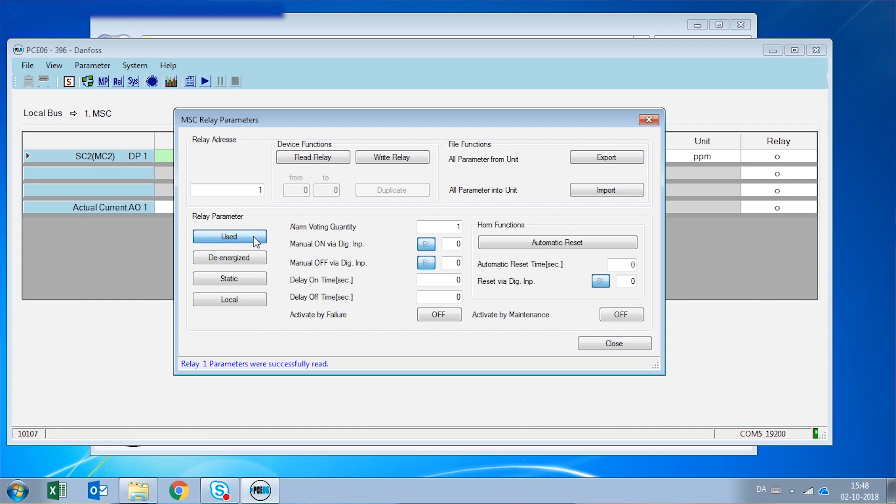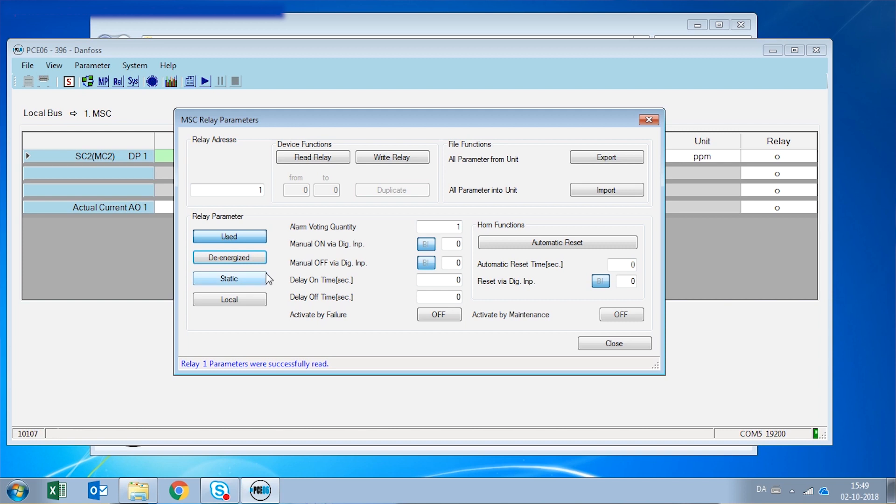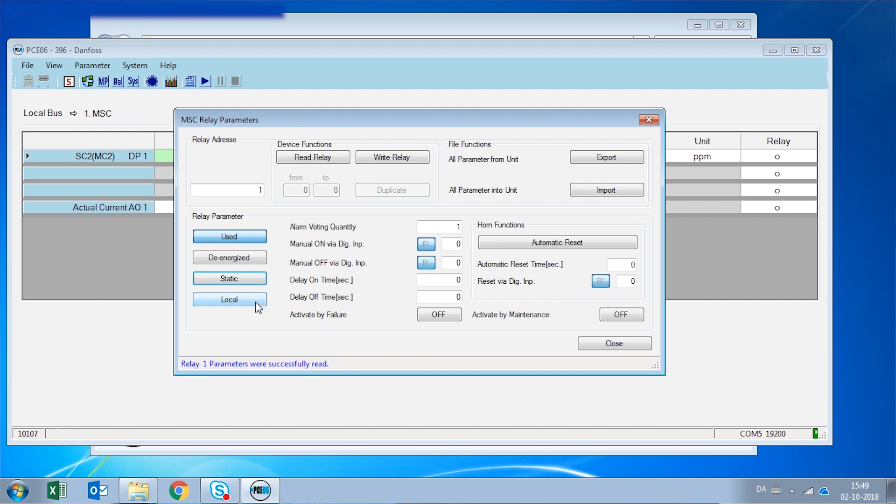Then you can see that the default setting of this relay is de-energized, which means that when there is an alarm it will energize, but we can change that to be the opposite. It is a static relay, but I can change it to be flashing. So when it activates it goes on and off. And it is controlled locally by this digital gas detector, but if I have a system that is connected to a central gas controller, I can change that to be controlled remote also.